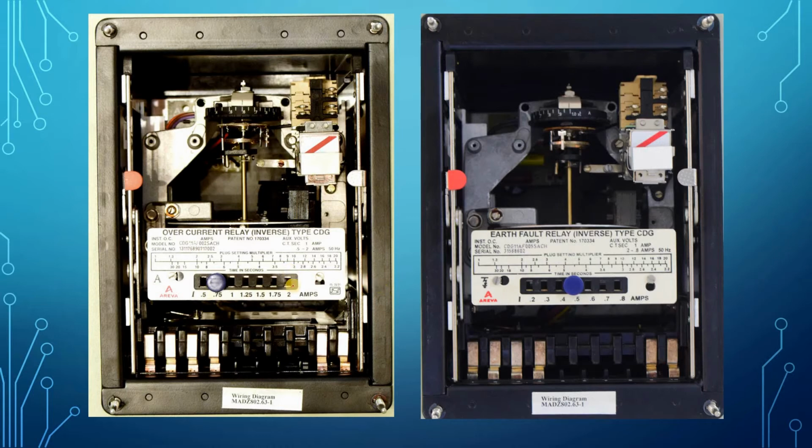As you know, overcurrent means this relay is generally placed in the phases of a supply, like RYB, from source to load. From the R phase this will be connected, the Y phase another relay will be connected. That means in series with the phase, this overcurrent relay will be connected. But this earth fault relay is generally connected between the neutral of the system and ground. In a three-phase system there will be 3 of this type of relay and 1 of this type of relay to protect the equipment.